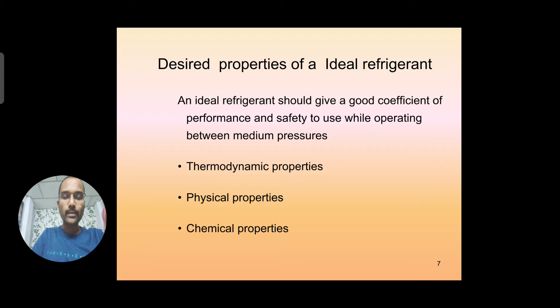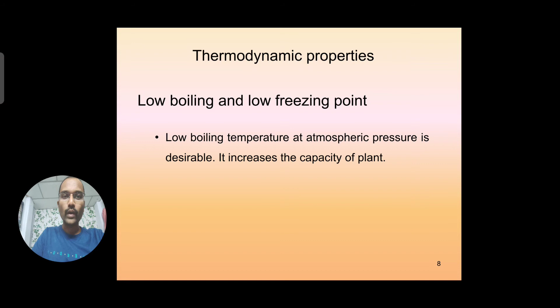The thermodynamic properties, first. Moving into this, the first of what we have seen in the requirements, that we are elaborately discussing here, these are the properties only. The low boiling and low freezing points, why they should be low. For example, first I want to explain regarding the freezing point. As we have seen in the VCR system, low temperatures are created in the evaporator, right? For example, some temperature attained in the evaporator is like minus 10 degrees centigrade. If that refrigerant is providing minus 10 degrees centigrade, what is the freezing point of that particular refrigerant? So we have to get some idea regarding the freezing point of a particular refrigerant, whatever you are using in a different application.